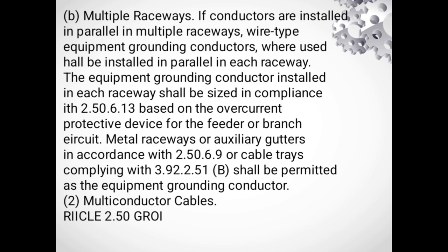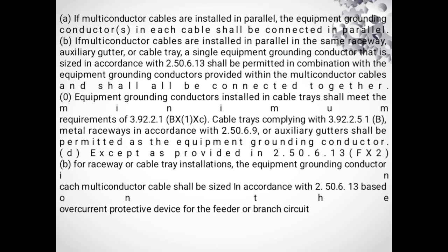Multi-conductor cables. If multi-conductor cables are installed in parallel, the equipment grounding conductors in each cable shall be connected in parallel. B. Multi-conductor cables installed in parallel in the same raceway, auxiliary gutter, or cable tray. A single equipment grounding conductor that is sized in accordance with 2.50.6.13 shall be permitted in combination with the equipment grounding conductors provided within the multi-conductor cables, and they shall all be connected together. Equipment grounding conductors installed in a cable tray shall meet the minimum requirements of 3.92.2.1. Cable trays complying with 3.92.2.51b, or metal raceways in accordance with 2.50.6.9 or auxiliary gutters, shall be permitted as the equipment grounding conductor.